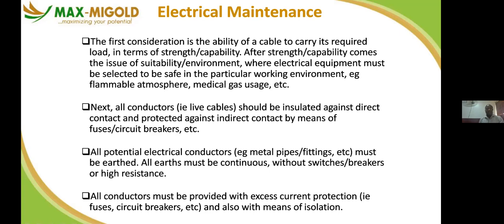So another one is all conductor, that is live cable, should be insulated against direct contact. You have to ensure that your installation is well protected, is well insulated against internal and external factors, the people that may be coming in contact with it. You may not be careful at all time or enough to know that this thing is live; before you know it, you must have touched it. To prevent that, you also ensure that they are well insulated against all factors.